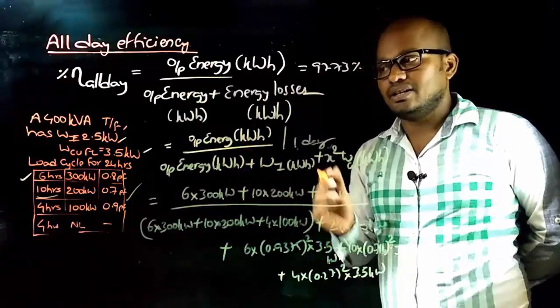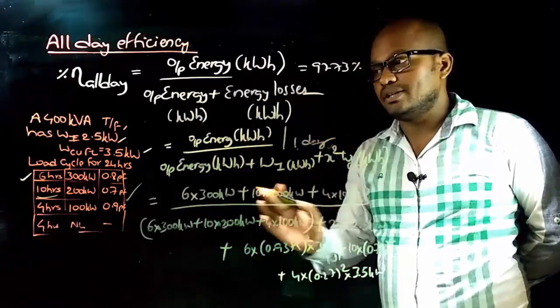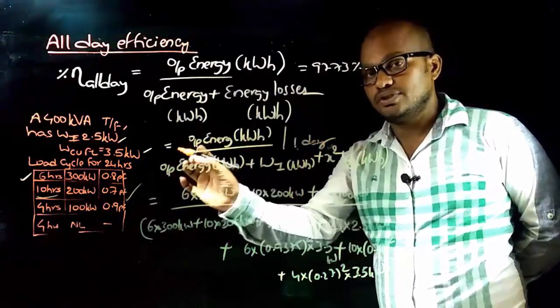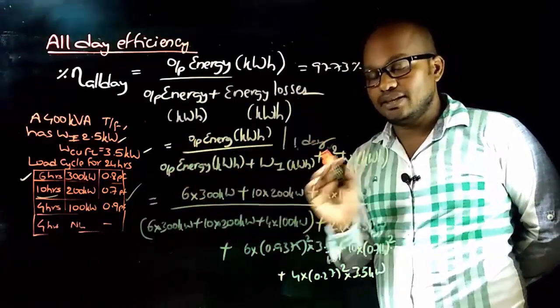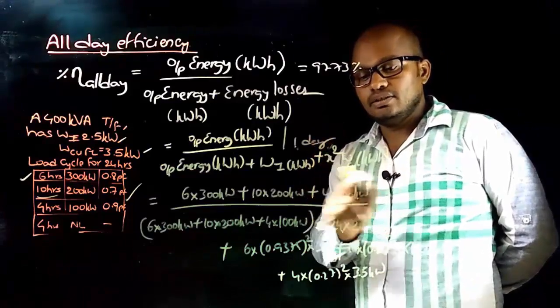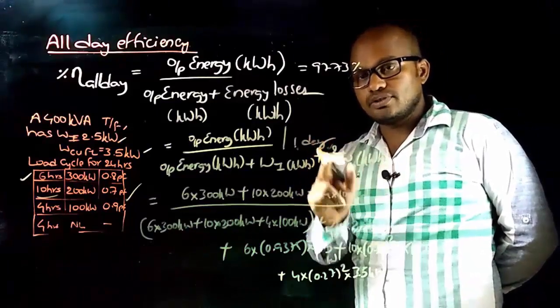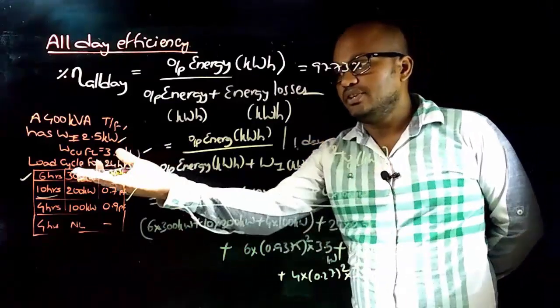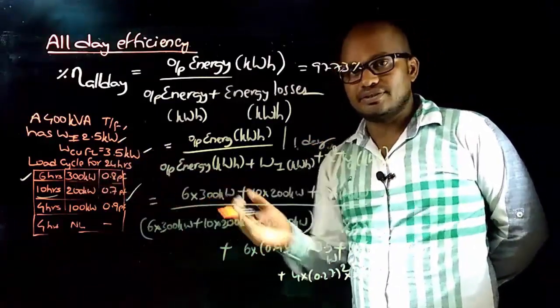This is how we find the percentage all-day efficiency of a distribution transformer using load cycle data. First, find x for each load period, then use x to calculate the copper losses for different durations.